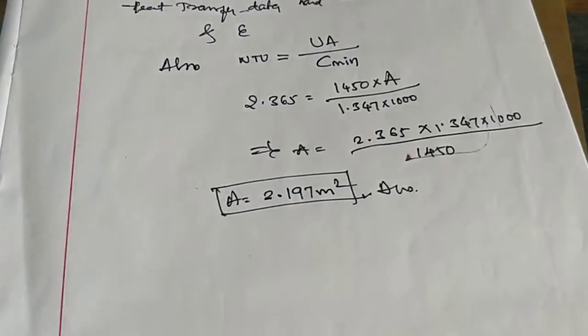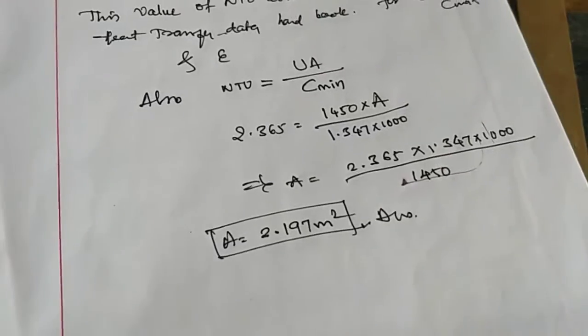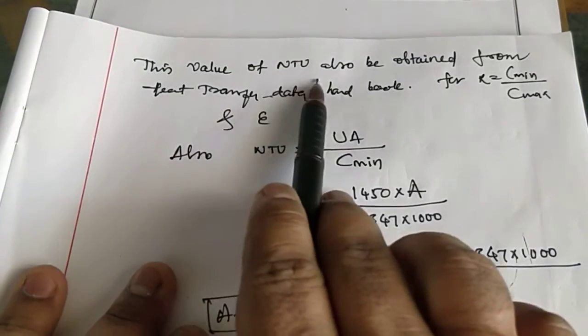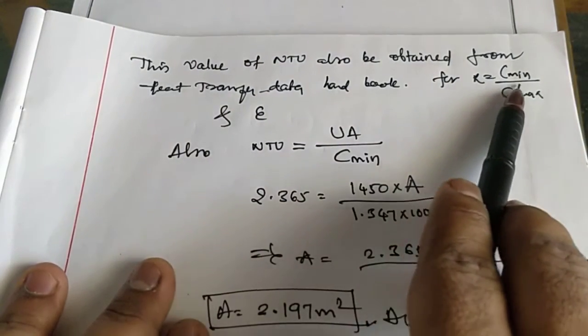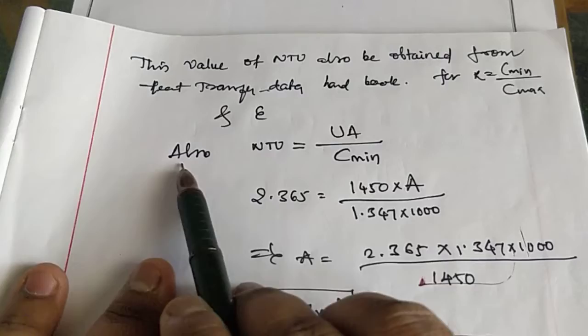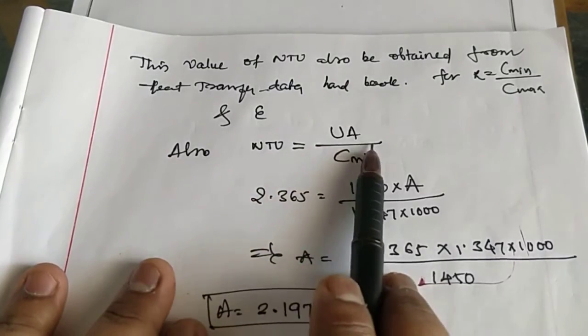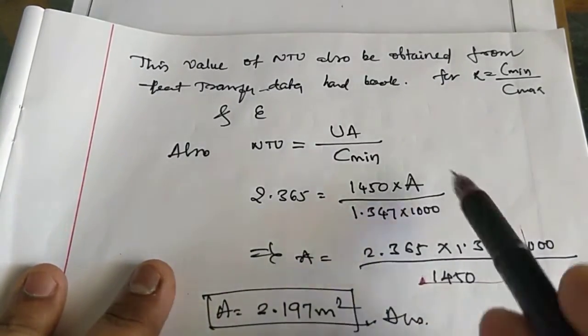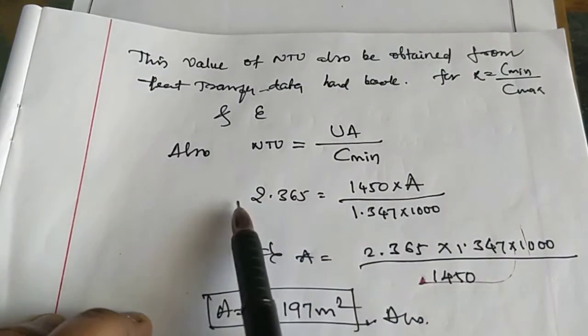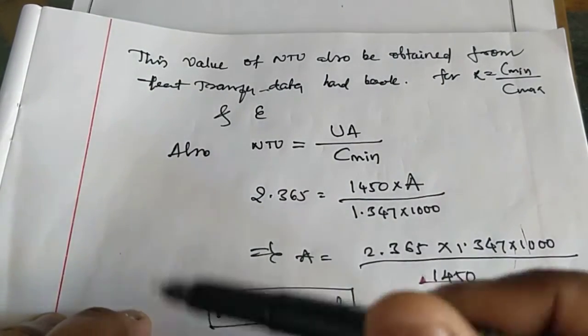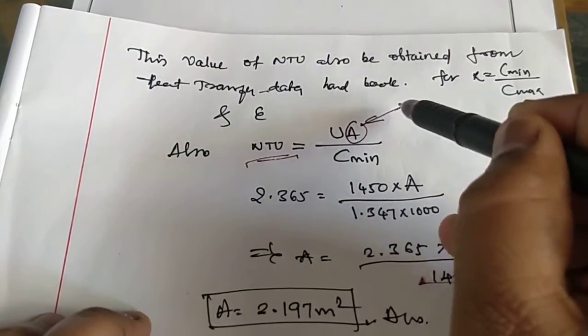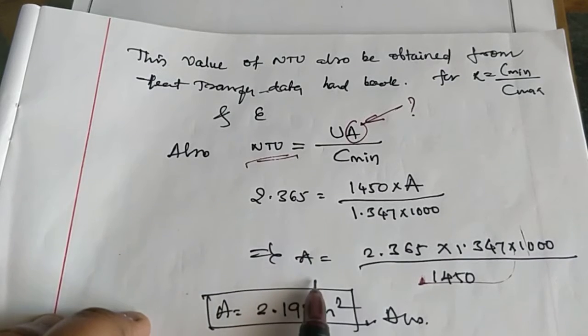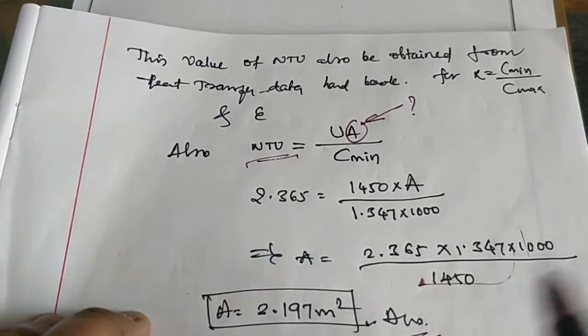Once the NTU value is obtained, we use the relation NTU = U × A / C_min to calculate the surface area. Substituting NTU = 2.365, U = 1450 W/m²°C, and C_min = 1347 W/°C, we get the surface area A = 2.197 m². This is the desired answer.